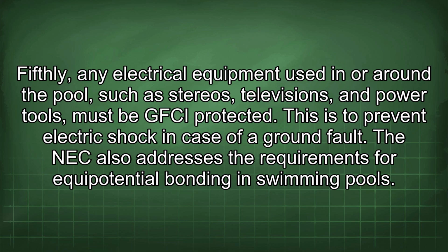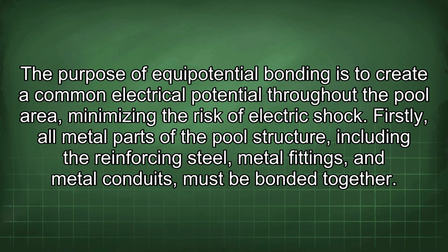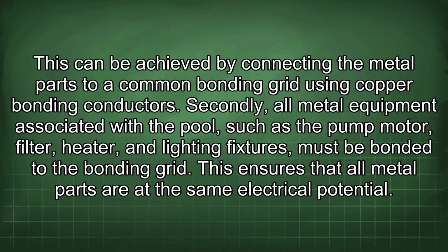The NEC also addresses the requirements for equipotential bonding in swimming pools. The purpose of equipotential bonding is to create a common electrical potential throughout the pool area, minimizing the risk of electric shock. Firstly, all metal parts of the pool structure, including the reinforcing steel, metal fittings, and metal conduits, must be bonded together. This can be achieved by connecting the metal parts to a common bonding grid using copper bonding conductors.